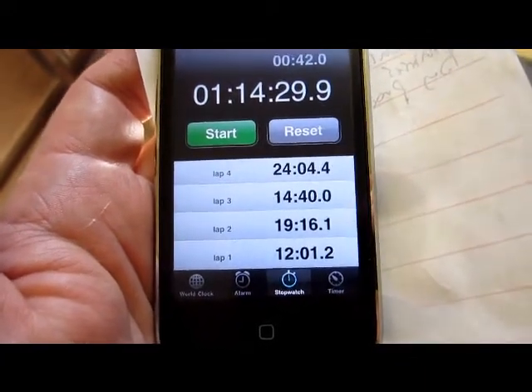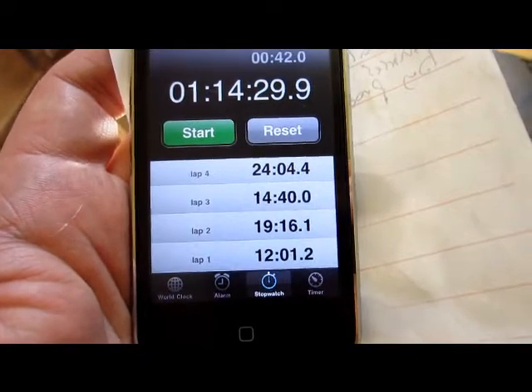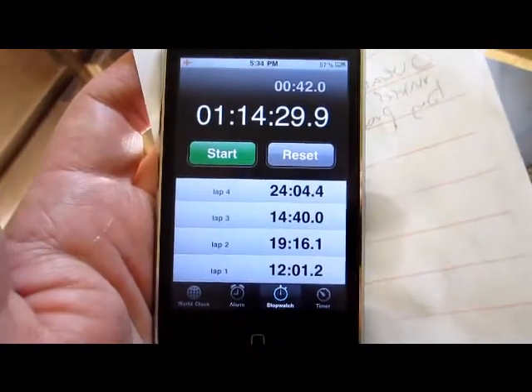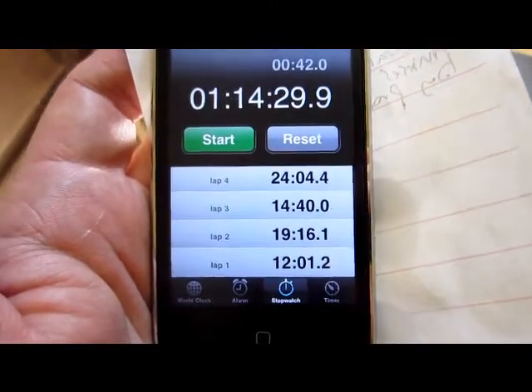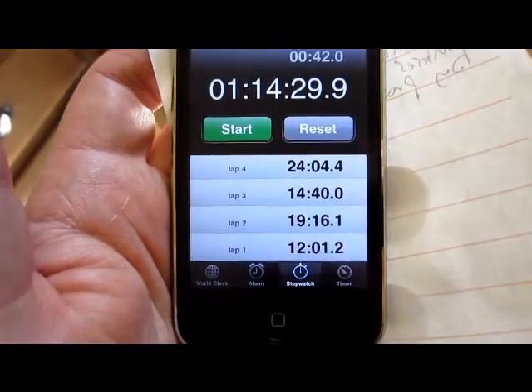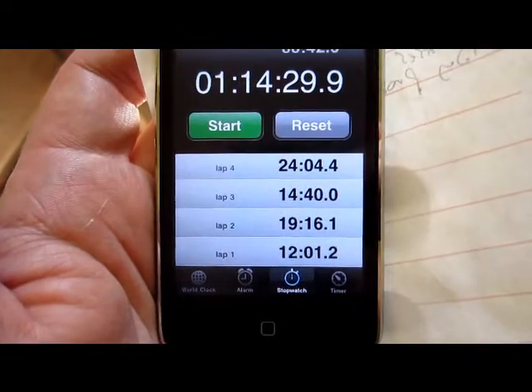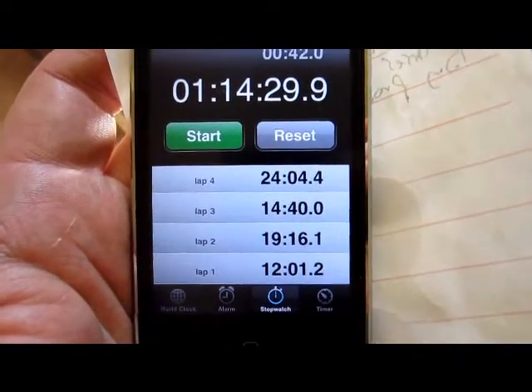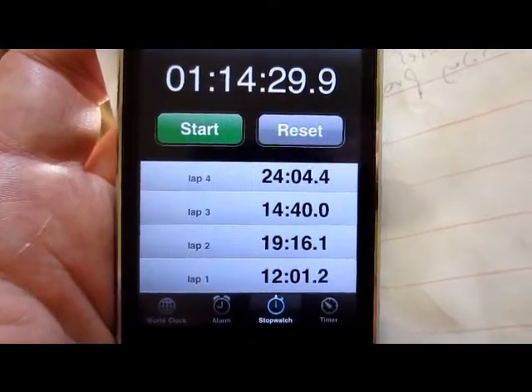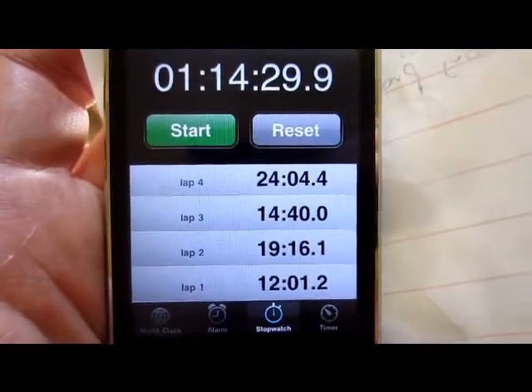So then, trying to determine whether it was heat related, I decided I would leave it cool. So I left the temperature right at 44 degrees Celsius. I took the temperature, didn't let it rise, and it kicked back on in 19 minutes and 16 seconds at, excuse me, 42 degrees. And then it ran for 14 minutes and 40 seconds, reaching 44 degrees and shut off.